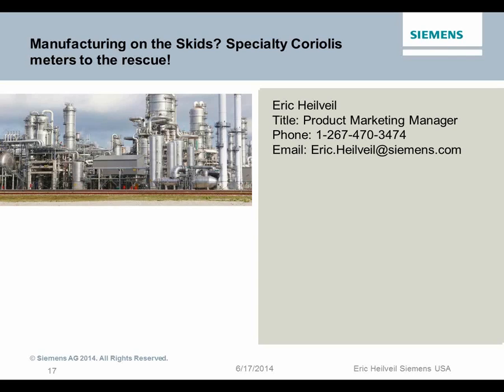And in the event that the micro SD card is also toasted, you can take your digital phone, your iPhone, or whatever digital phone du jour, scan the QR code on the outside of the meter, and get all of the calibration data from that sensor direct from the network through our servers, so that you can update your system in the field without having to contact your representative or Siemens. So you get your calibration data right there. So that's kind of handy. These are all some of the little things, but we are very comparable to the F-Series in Micro Motion, very, very comparable to the 83F in Endress.